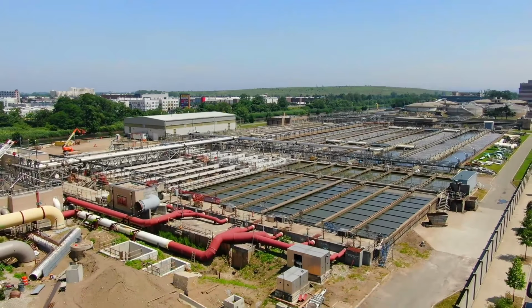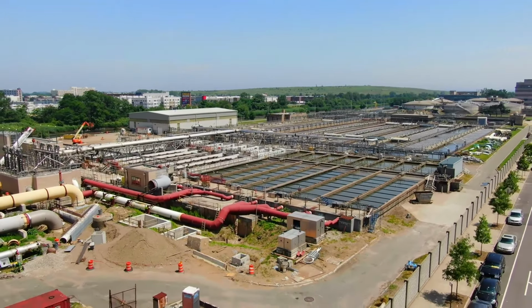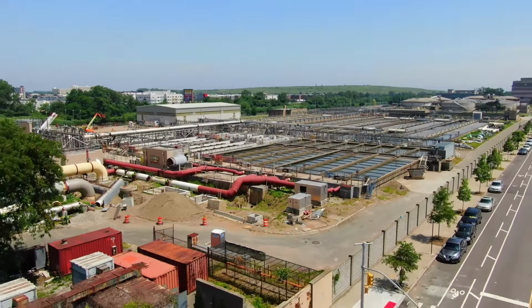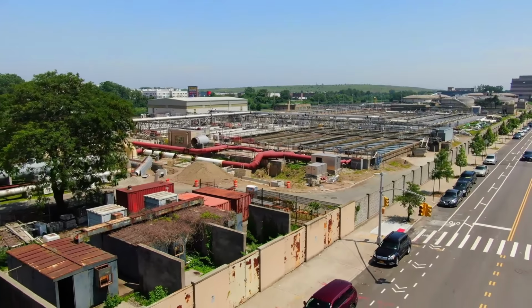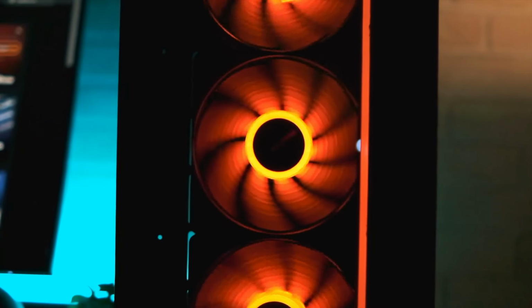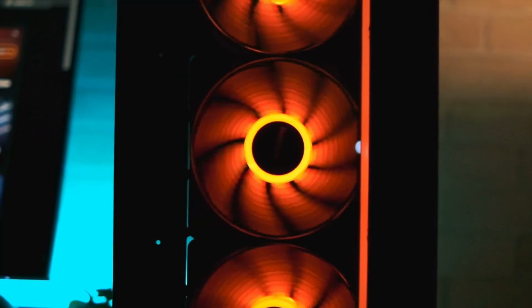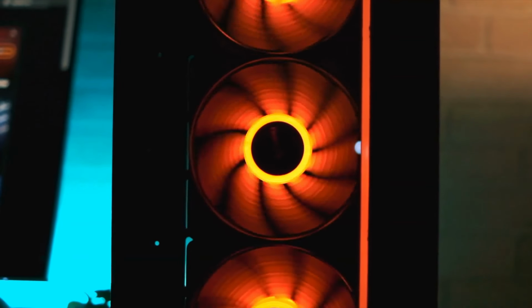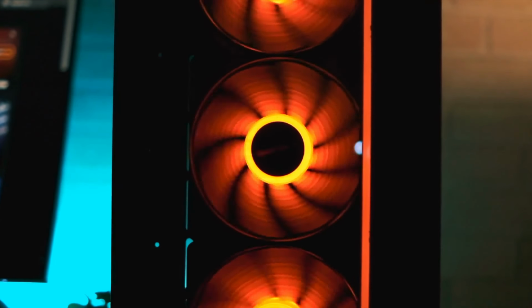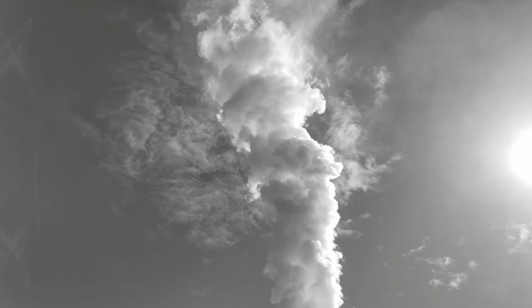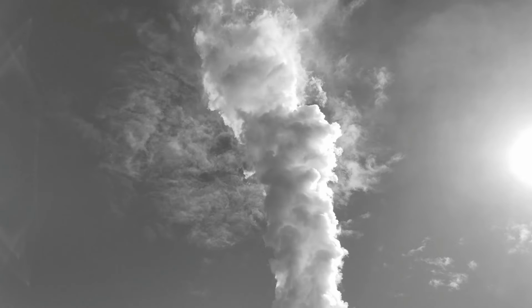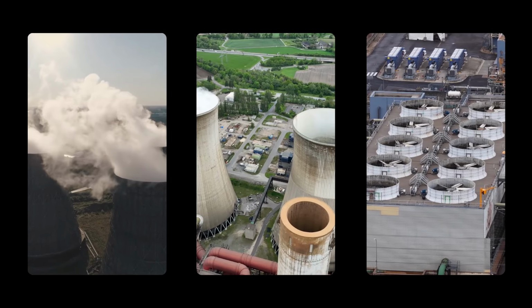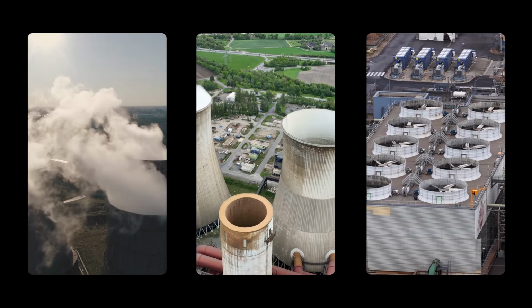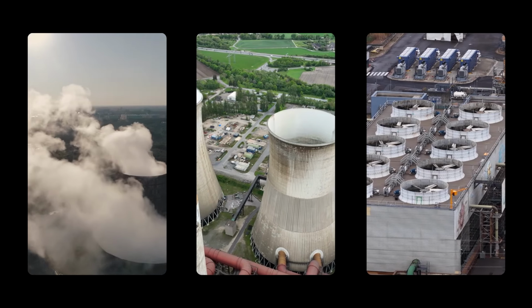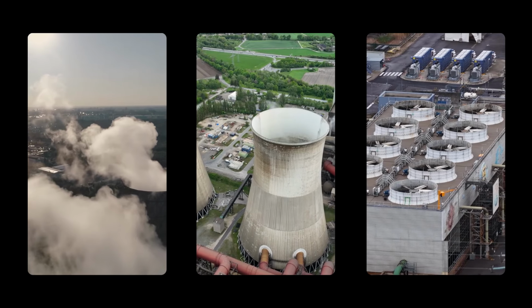The data center industry measures water efficiency using a metric called WUE, water usage effectiveness. Liters of water consumed divided by kilowatt hours computing delivered. An air-cooled data center, one that rejects heat only using fans and radiators instead of evaporative water cooling, would score 0 on that metric. And that's how it shows up on the sustainability reports. The thing about electricity is, depending on what kind of power plant was used to generate it, the process may consume much more water. Coal plants and nuclear plants work by boiling water to spin turbines. That steam needs to be condensed back into liquid to be cycled through again, which requires rejecting heat to the environment. Most plants do that with cooling towers.